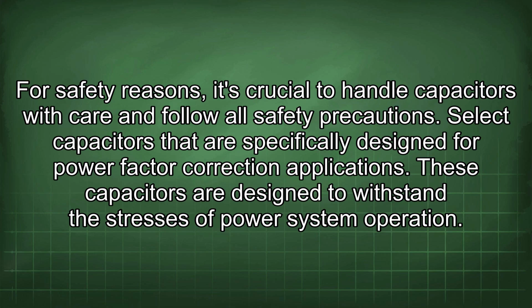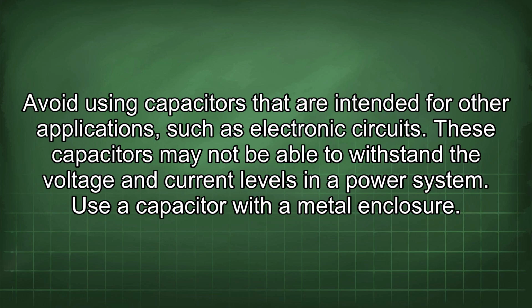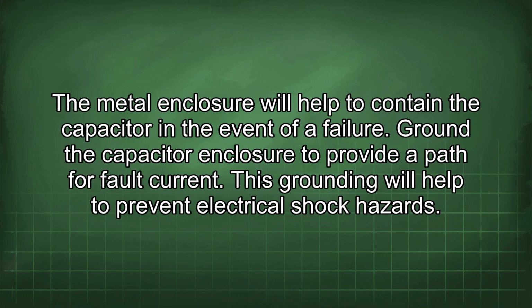Select capacitors that are specifically designed for power factor correction applications. These capacitors are designed to withstand the stresses of power system operation. Avoid using capacitors that are intended for other applications, such as electronic circuits. These capacitors may not be able to withstand the voltage and current levels in a power system. Use a capacitor with a metal enclosure. The metal enclosure will help to contain the capacitor in the event of a failure. Ground the capacitor enclosure to provide a path for fault current. This grounding will help to prevent electrical shock hazards.